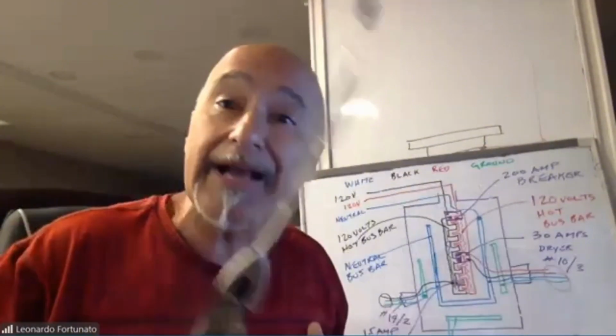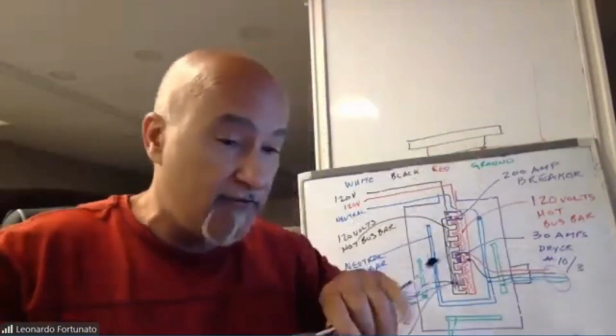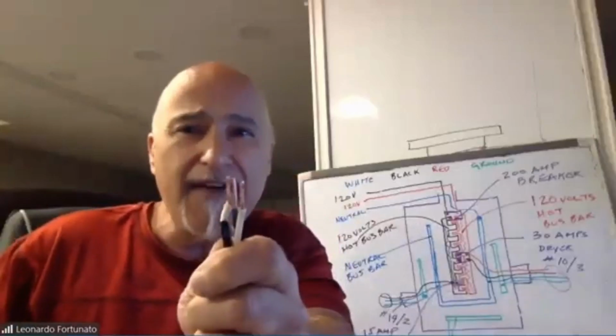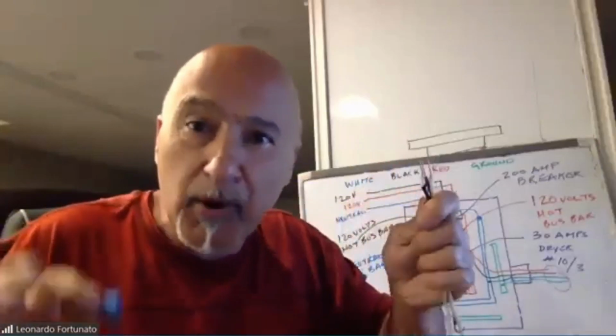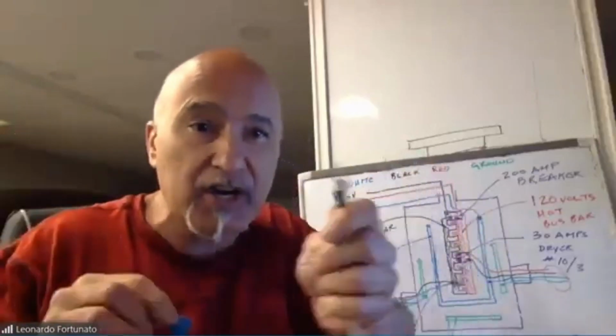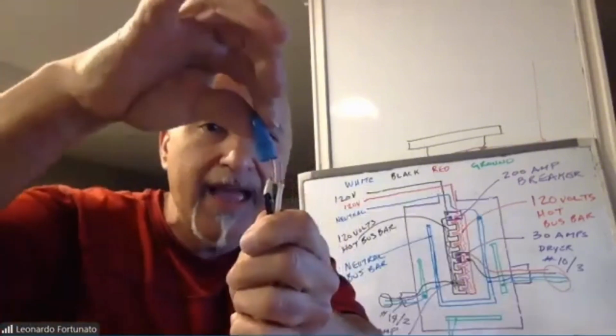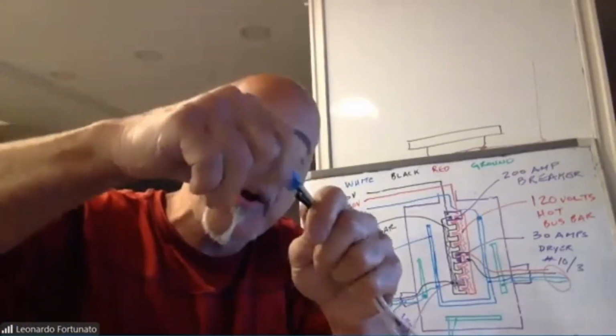Another tip: when you're going to make a connection with a wire nut, never do this. Some people are afraid and don't want to touch anything, so they just put the wires close together, then put the wire nut on, relying on the wire nut to keep them together.